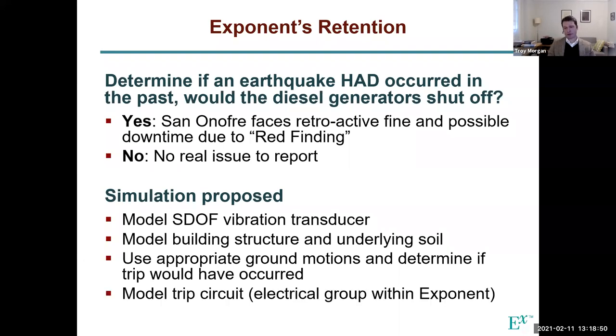And then we also had to model the trip circuitry, because remember, this vibration measurement device measures movement and then spits out a voltage. That voltage then goes to a series of signal conditioners and relays. And then there's a control system, an electrical system, that takes that measurement and makes a decision: do we trip this thing off because it's malfunctioning, or do we not? That's kind of how things work.